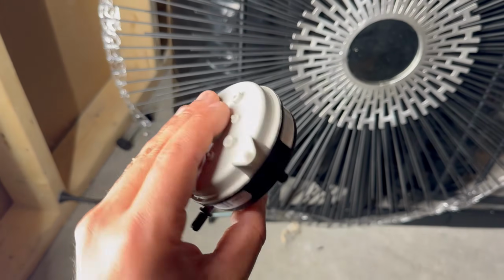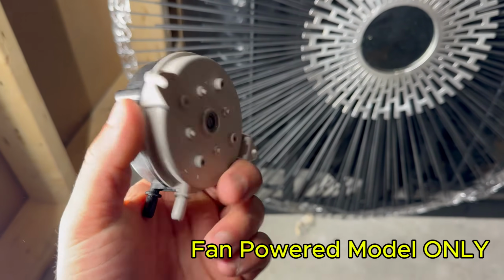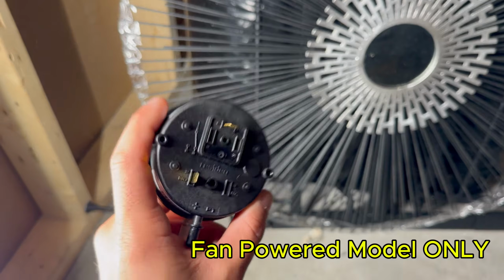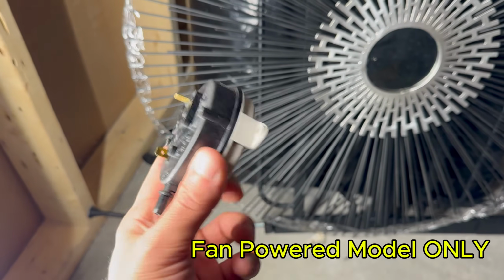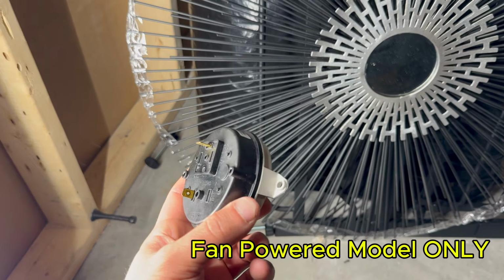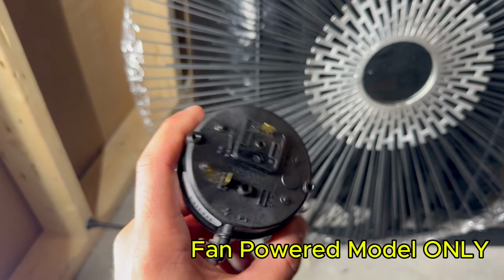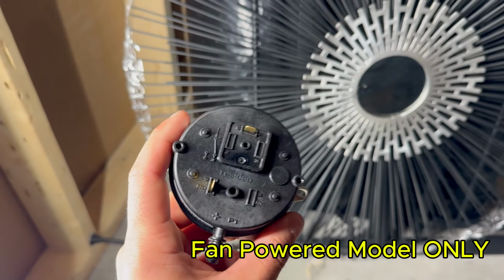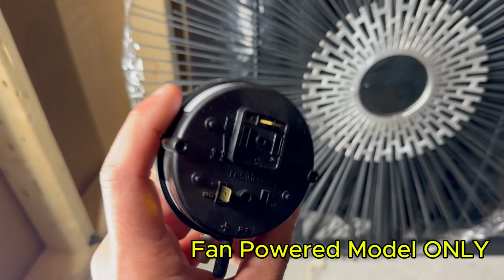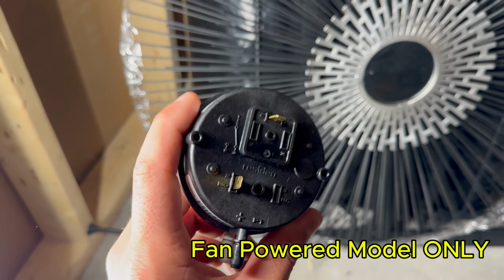Now we've got our pressure switch, and what this is going to do is control whether or not you are going to turn on your humidifier when the humidistat tells it to. In other words, this is going to detect when the furnace is actually running, and then if the humidistat is asking for humidity, this will allow it to run.